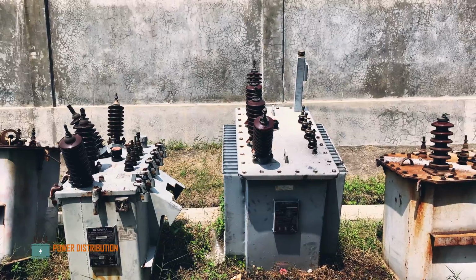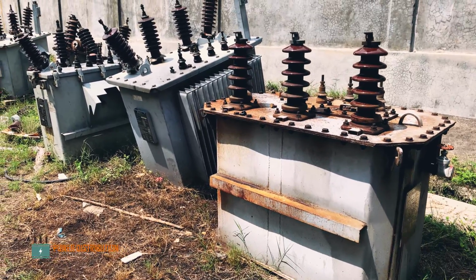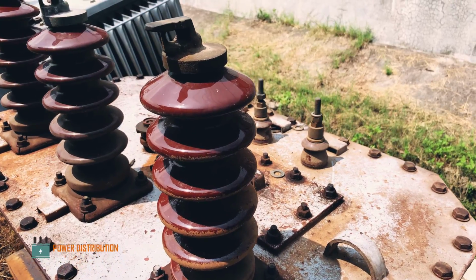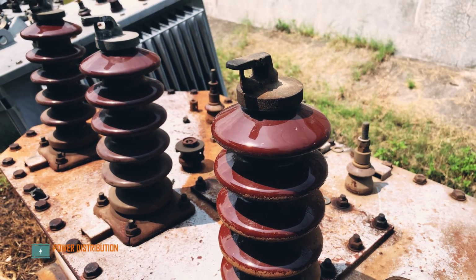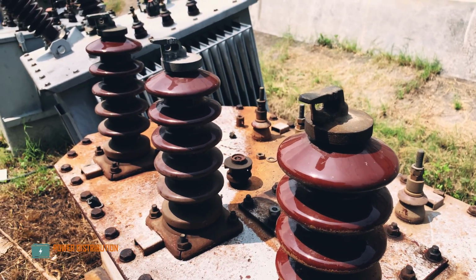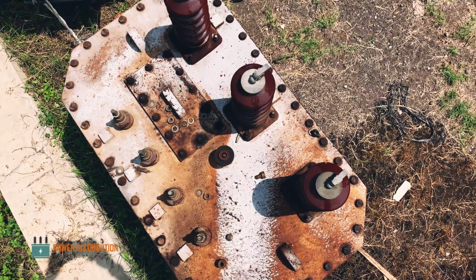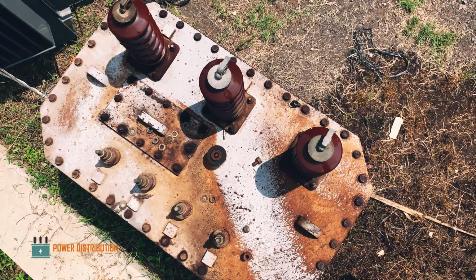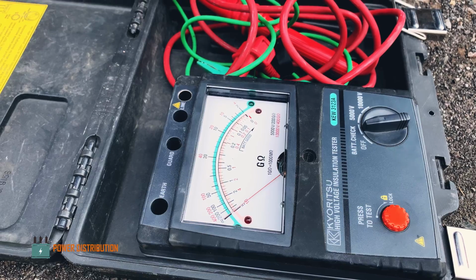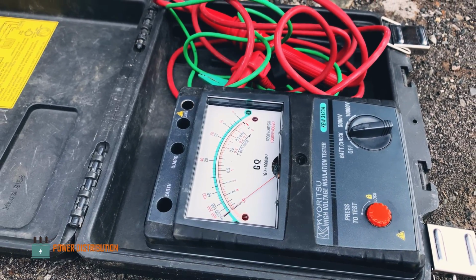In this very bright day, I am going to do an insulation test or hypot test, or commonly called Megger test, on a three-phase distribution transformer. In this process, I am going to use a very versatile equipment called a high voltage insulation tester.